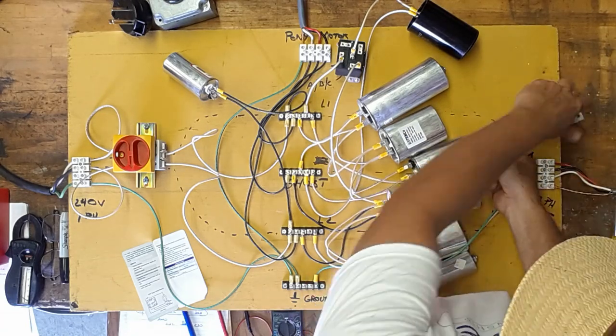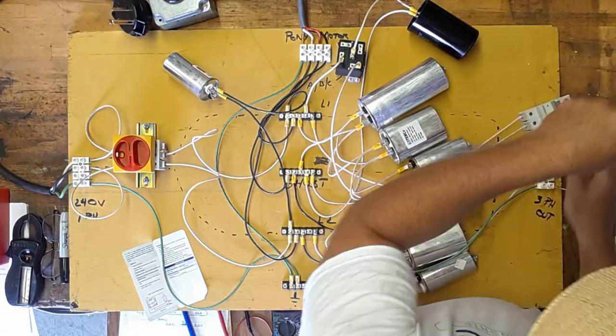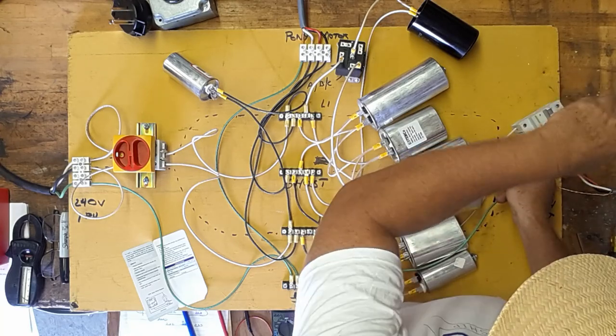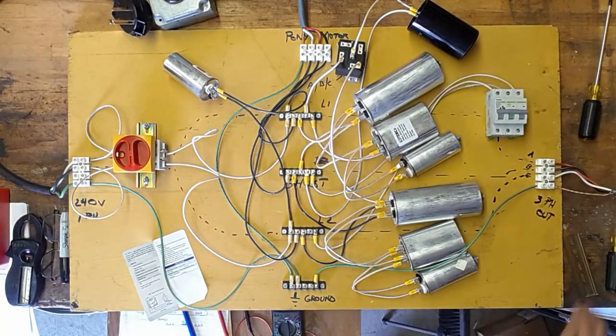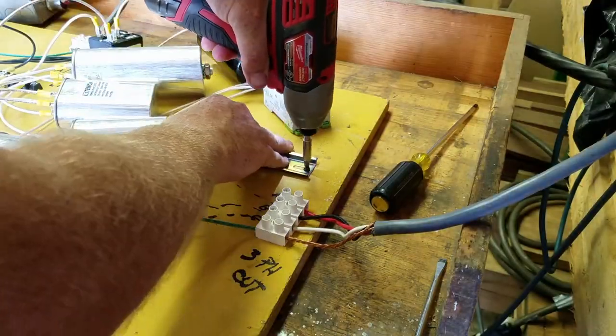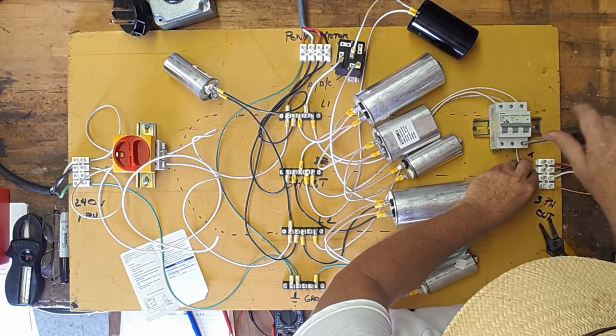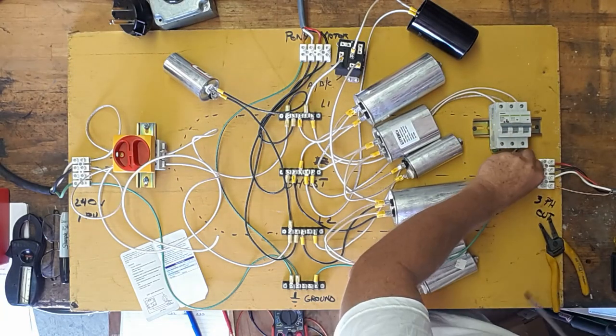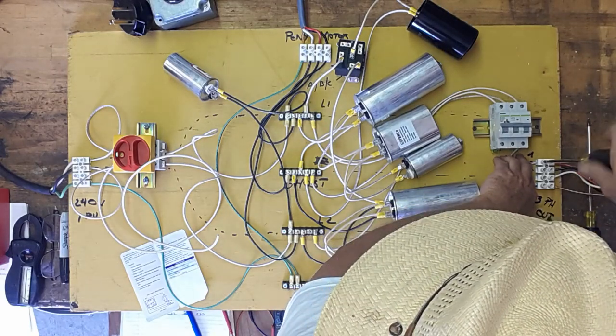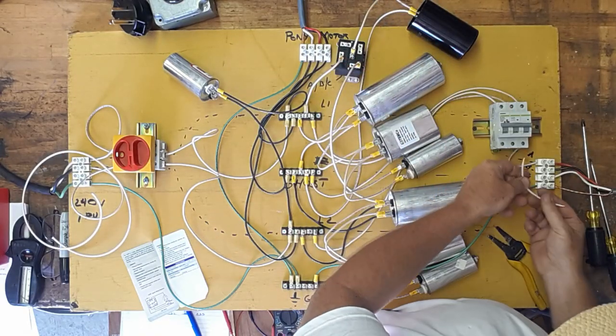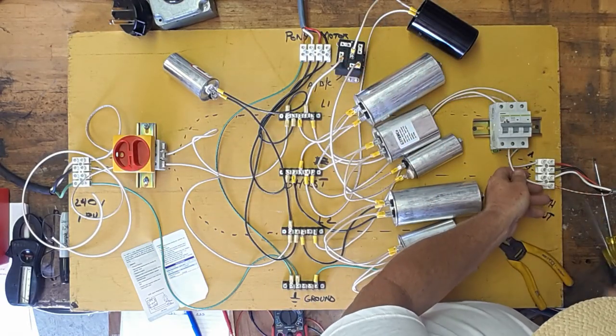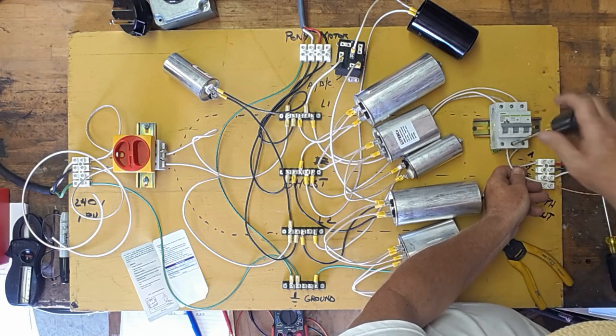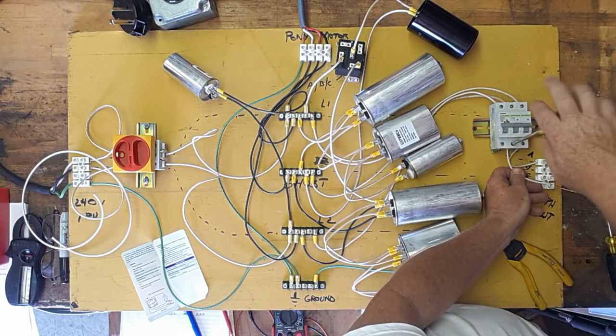From the original layout, the number one thing I wanted to add to provide some safety was a circuit breaker on the outbound side of the phase converter. This will protect against short circuits and overloads on any downstream equipment. And I think it's critical to any of this type of thing you do. The incoming side of the phase converter will be protected by the breaker that's in the panel it'll be wired to. So that end's covered.